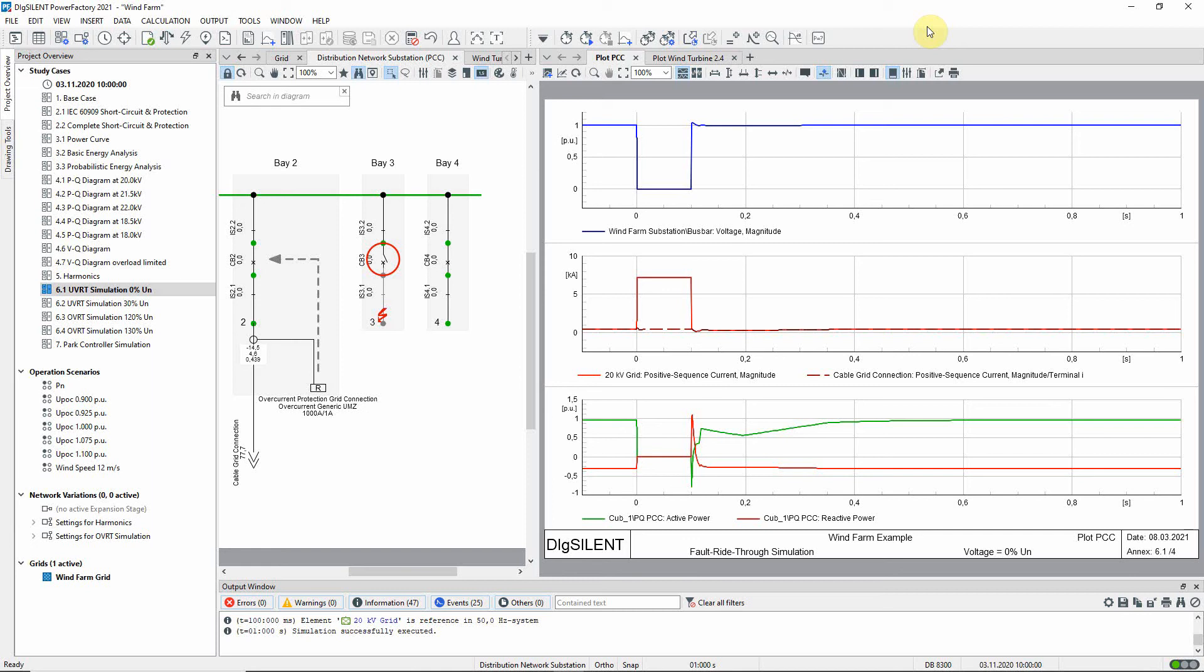In the second plot, the positive sequence current contributions from the external grid and from the wind farm are shown. It can be seen that during the fault, the contribution from the grid is very high. The bottom plot shows the active and the reactive power contributions from the wind farm. It can be seen that during the fault, since the voltage at the point of common coupling drops to zero, the real and the reactive power also drop to zero.